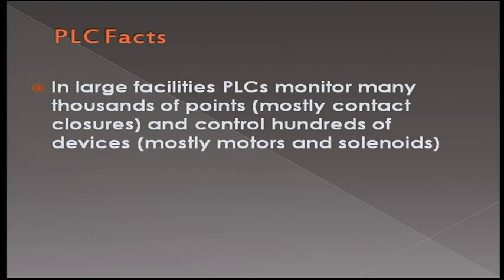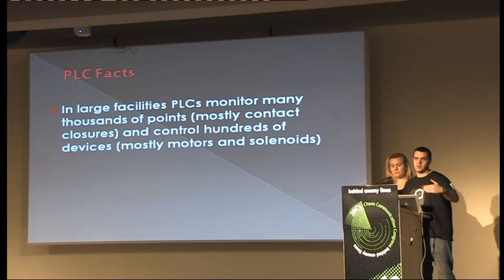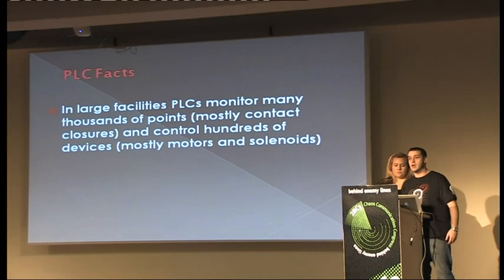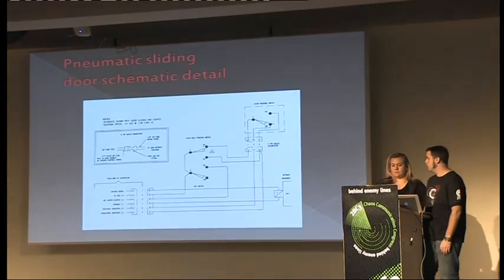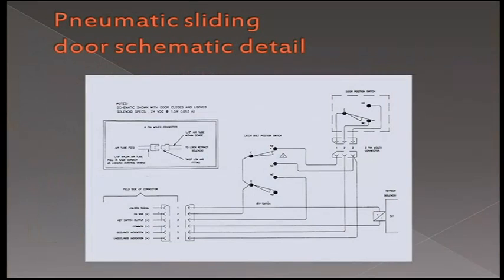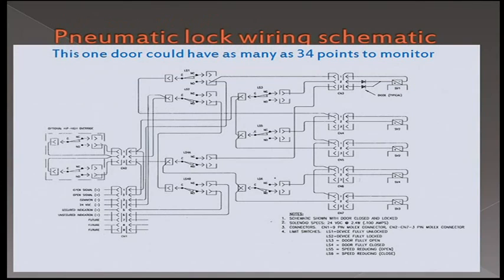Within a large facility, these PLCs may monitor thousands of points. With a prison door, it can be controlling the solenoid that controls the lock state — is it locked or unlocked? But then it's also going to monitor the door, like how far open or closed a sliding door is. On this particular schematic, you can monitor up to 34 points on that door. A lot of times, PLCs are implemented to cut down on hardware costs — conduit and actual wiring. You can run all these wires back to central control from every single point, or run them to a PLC and run one wire from a PLC back to central control.